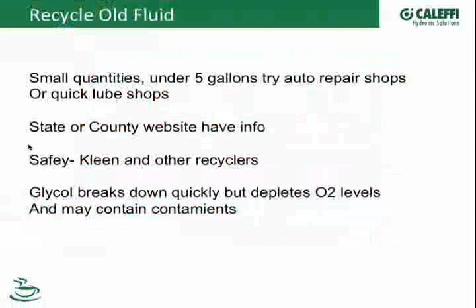Recycling old fluid, what do you do when you take some out and want to replace it? For small quantities, I've been able to take a couple of 5-gallon buckets to an auto repair shop or a Quick Lube. They already drain radiators and put glycol in a drum to recycle. Somebody comes and picks that up and buys it. Your state or county website might have info on a recycler. For large quantities, we've used Safety-Kleen before, hundreds of gallons like a school or university project where it has to be taken out and disposed of. You can hire them, and they document it and make sure everything is done properly and legally, so you have that sheet to prove it was handled correctly.